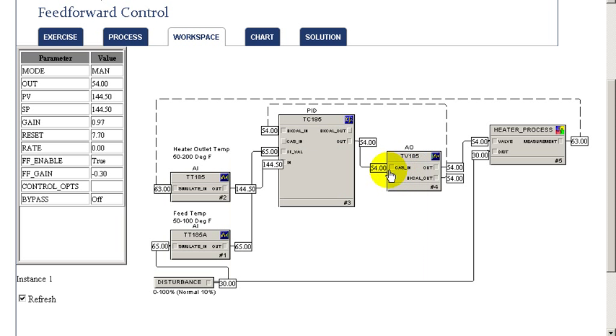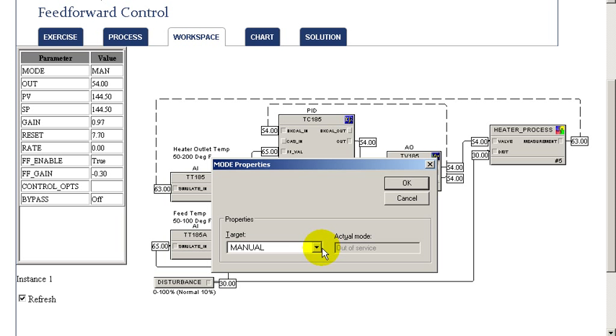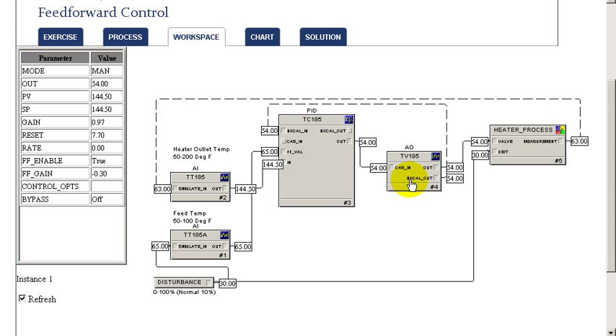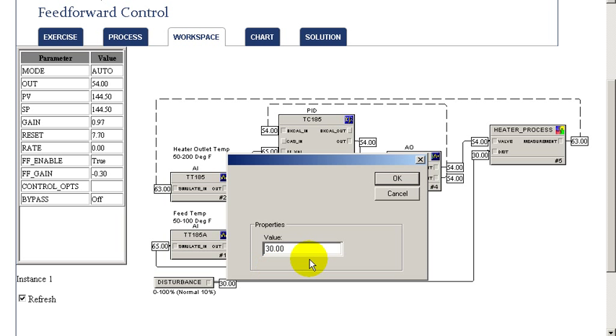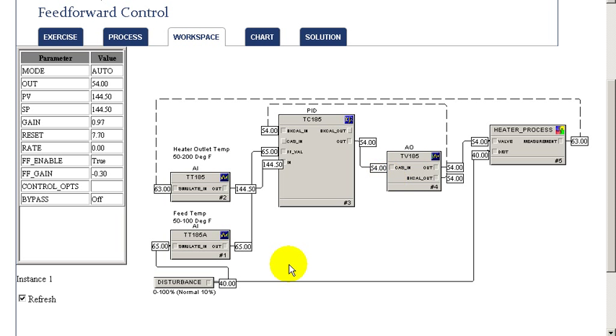To set up our feedforward, we're going to change the feedforward gain to our calculated value of minus 0.3, and we're also going to enable our feedforward. Once we have enabled this, we're going to put our controller into automatic mode. As you notice, the temperature is maintained and the temperature set point has been following the temperature, so there's no bump when we go to automatic. We now introduce another 10% change in our disturbance input. The controller immediately compensates as the output changes, even though there's been no change in the actual measurement.